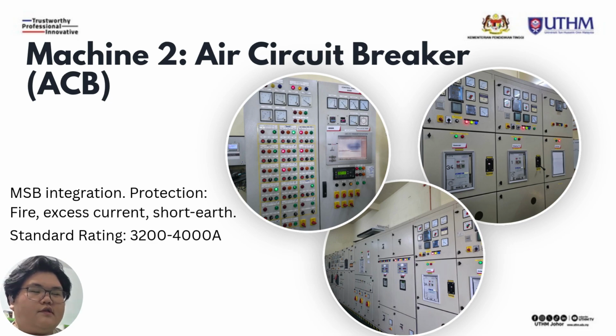So the standard rating for the ACB is around 3,200 to 4,000 ampere. So any current above that range will cause the air circuit breaker to function. It will break the circuit, so the damage to the system is not very big.